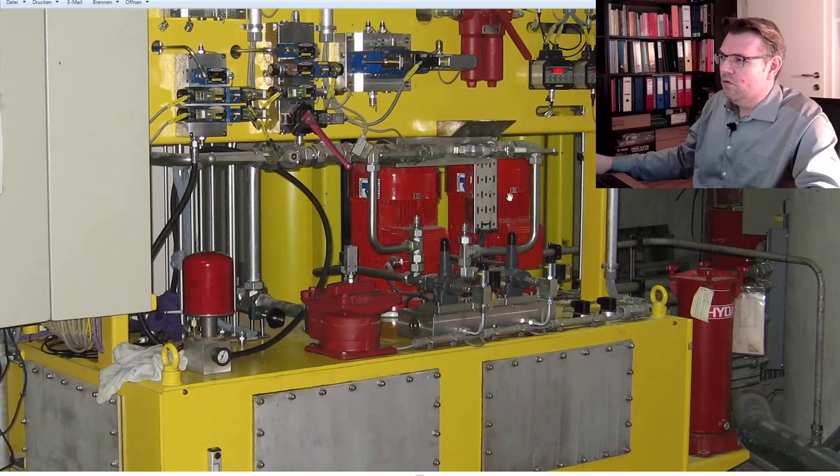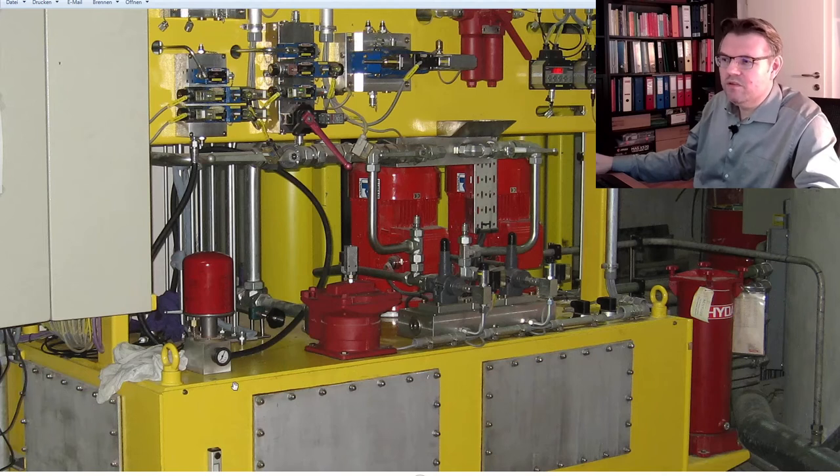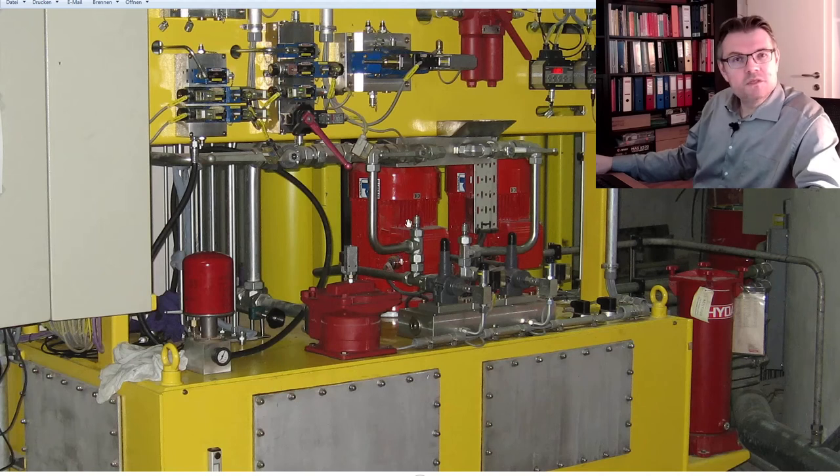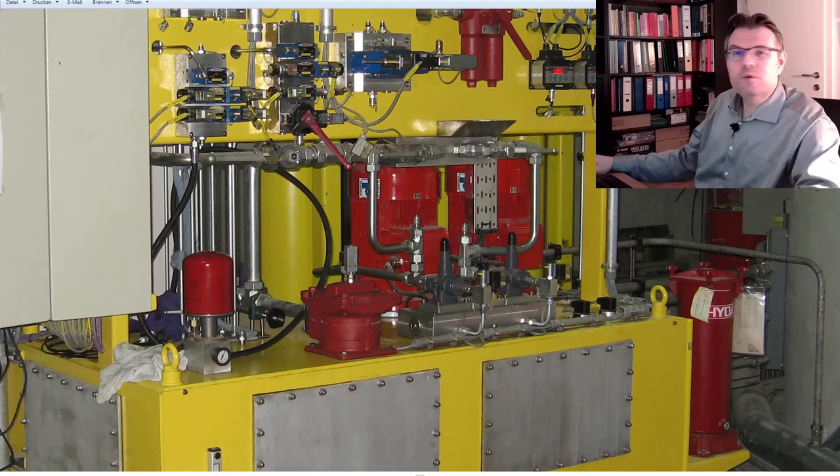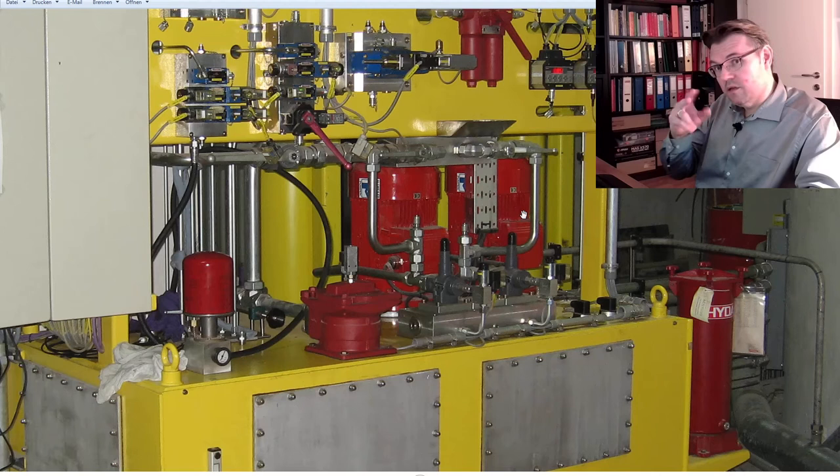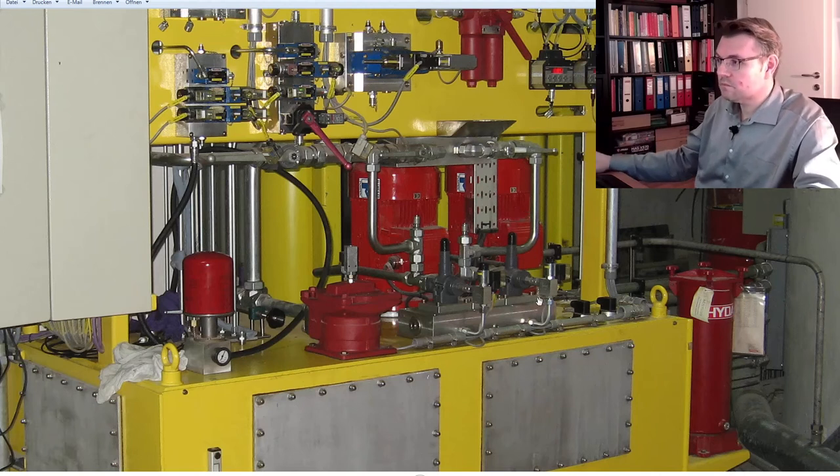Those two things in the back, the red ones here, those are the motors for the pumps. The pumps are underneath the cover. So there are screw-type pumps here, two screw-type pumps. Usually only one is in operation, but they're changing operational. And only in times when really a lot of oil is needed by the hydraulic system, we can even start a second pump.